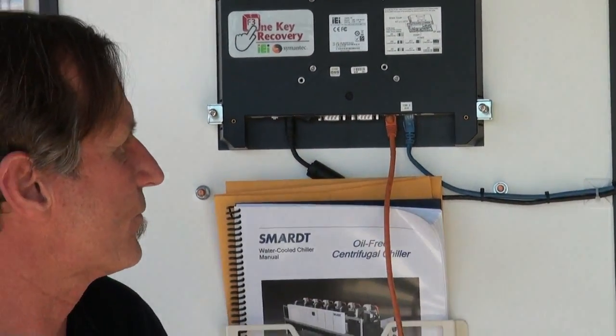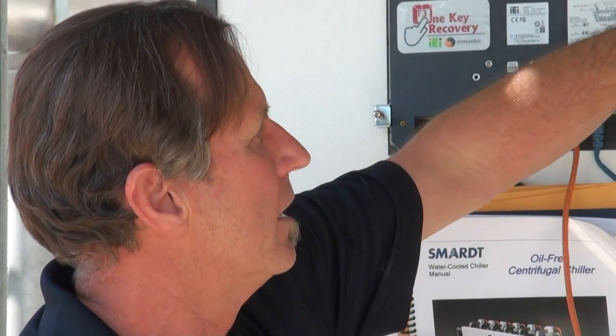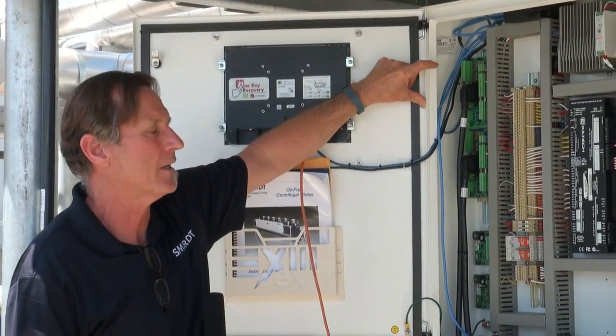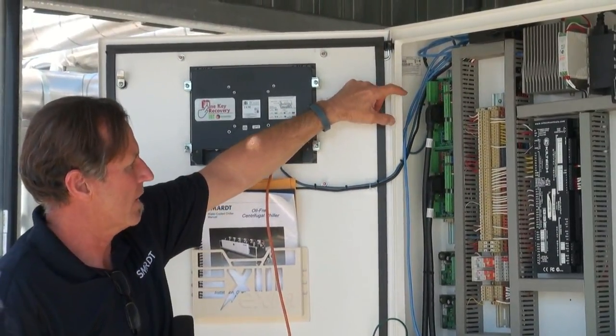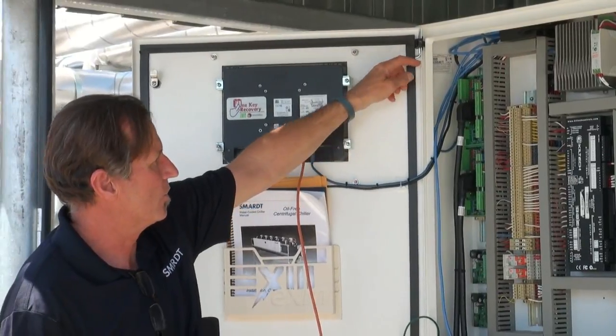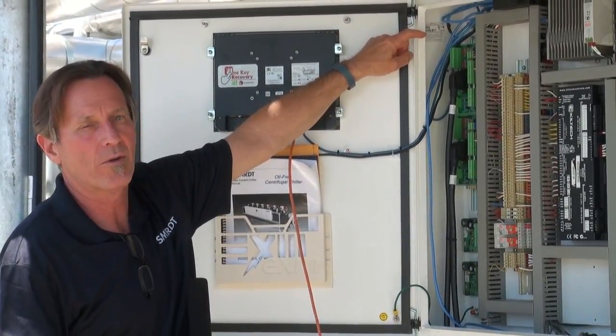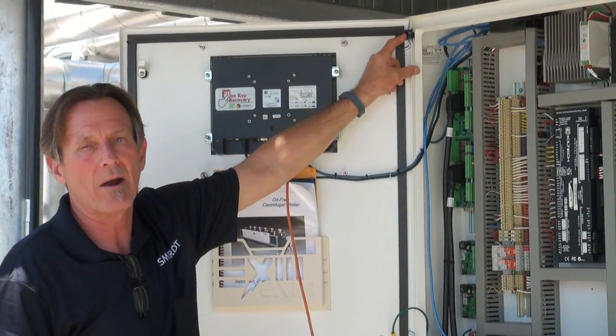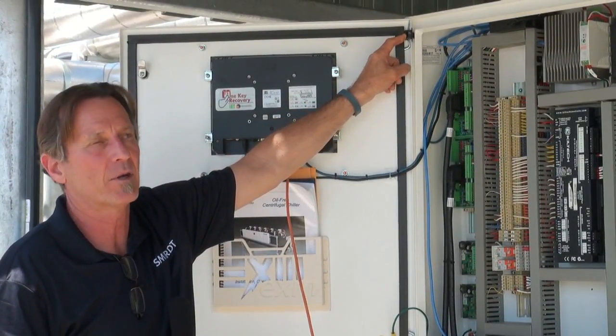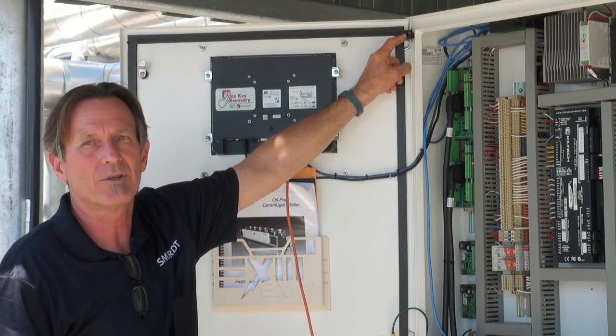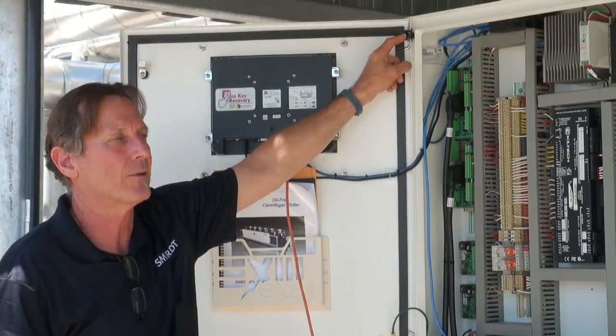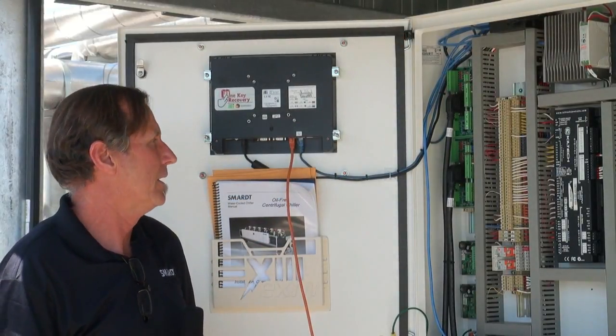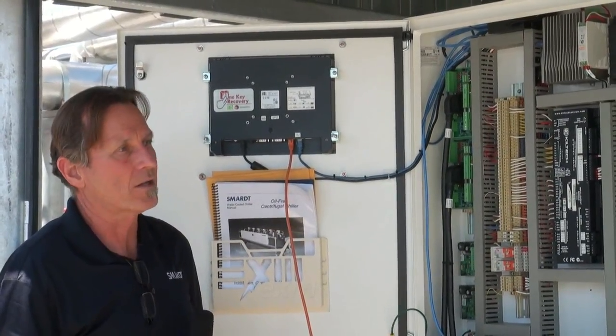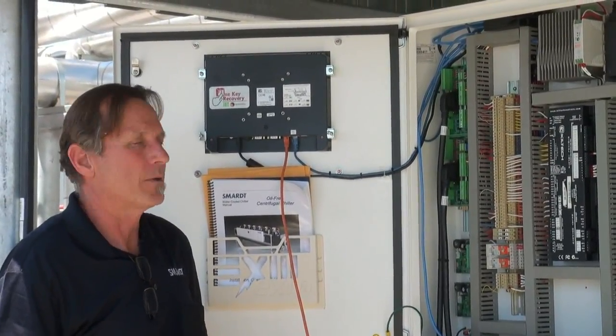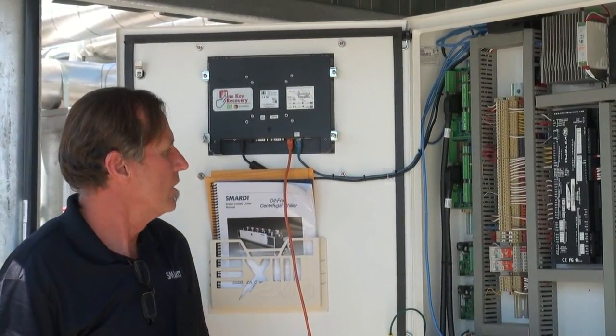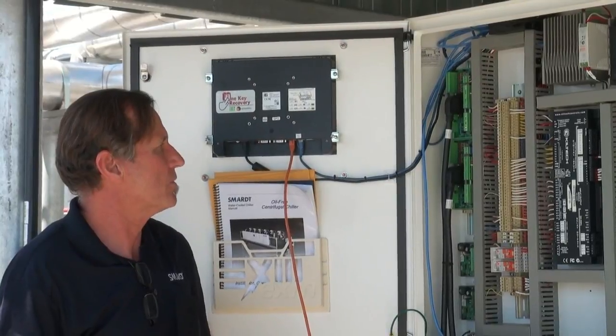But inside the panel, we talked earlier about the interface to each compressor. These green boards here on the left-hand side of the panel, you've got two there, one for each compressor. You'll notice there's a green light in the upper right-hand corner of the board. If you lose power to the compressor, that light will go out. So if you have a compressor that's not running, you can eyeball that light and say, well, there must be a problem with the power on my compressor. That green light is out. It could be a problem with the compressor, you check the feed, could be a fuse, could be anything. So that's our interface to the compressors.